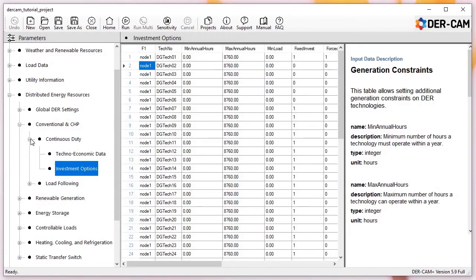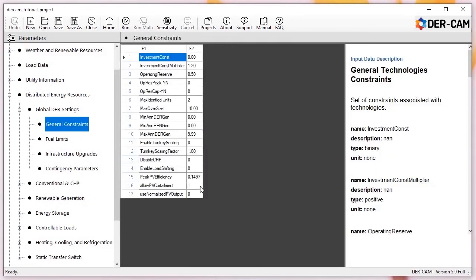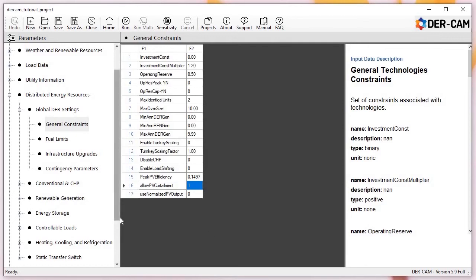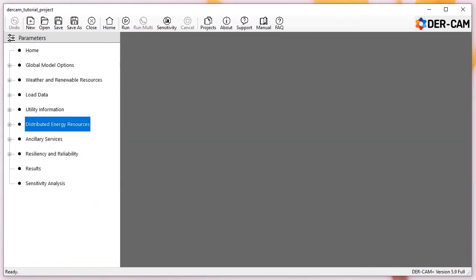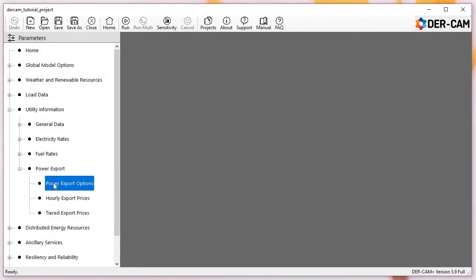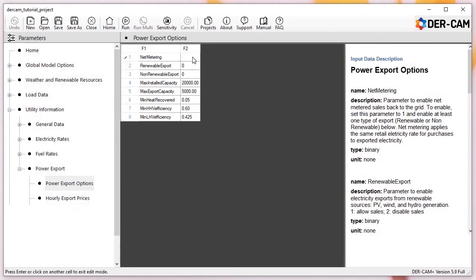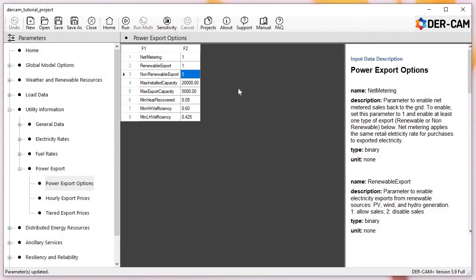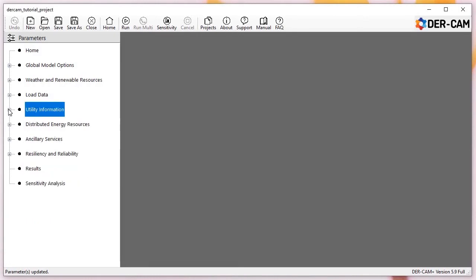Before running our case, let's check a few minor options. In our DER menu, navigate to General Constraints. For this case study, check to see that Allow PV Curtailment is enabled. This isn't required, but if you've selected different input options, your model solution might vary from the one presented here. Next, we're going to enable exports from PV. Under Utility > Power Export Options, we'll enable net metering and exports from renewable sources. The net metering option sets the export price to the retail rate and prevents the site from exporting more than it imports over the course of the year. With these two minor changes made, we're again ready to save and run our model.